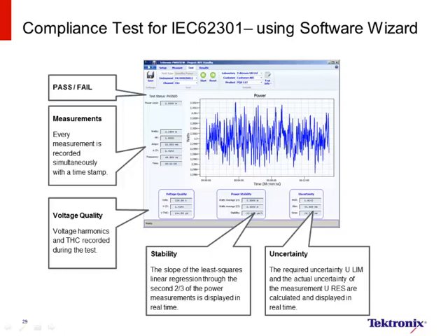MCR is used to calculate the required uncertainty of the measurement. All of these measurements are taken continuously and logged to disk for reporting by the automatic software. Different standby power limits apply to different products and programs, of course. 50 to 500 milliwatts is a typical limit.